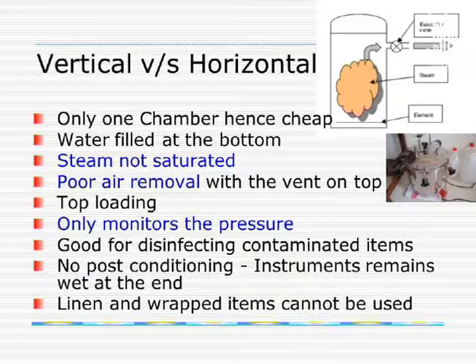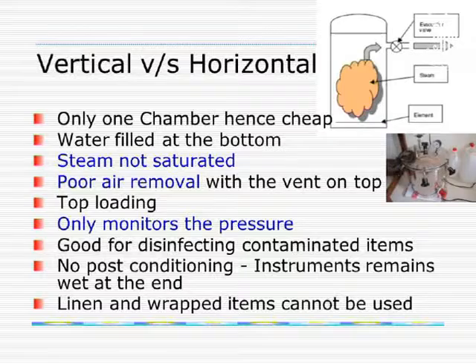Without going into too much detail about vertical versus horizontal autoclaves: the vertical has the problem of air removal — the vacuum process is not very perfect because it works only by gravity. The horizontal autoclave, which has a separate chamber for steam, is far better than the vertical.